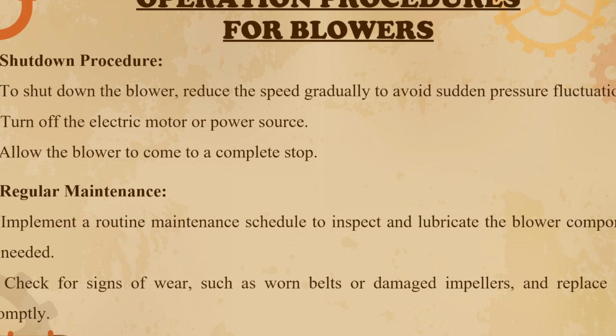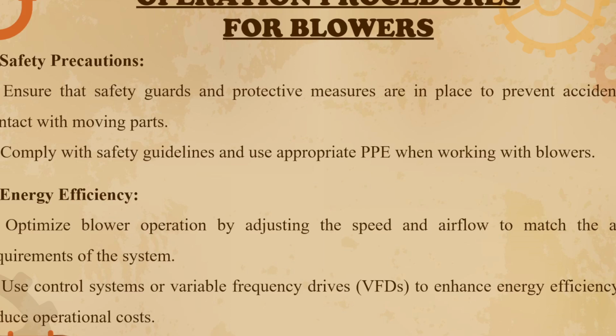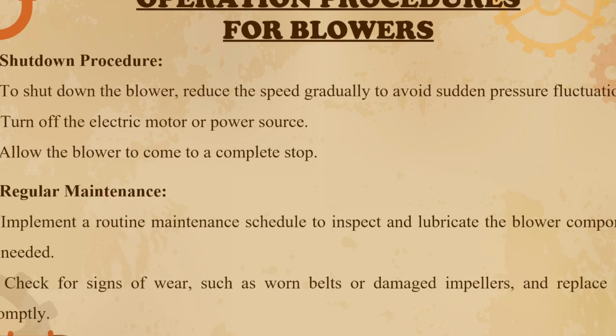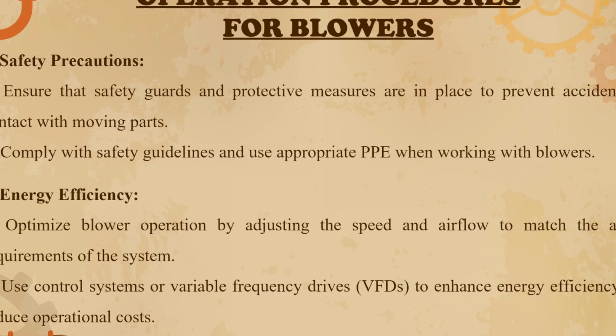Sixth procedure is to have regular maintenance. Implement a routine maintenance schedule to inspect and lubricate the blower components as needed. Check also for signs of wear, such as worn belts or damaged impellers, and replace them promptly. Seventh procedure is the safety precaution. We must also ensure that safety guards and protective measures are in place to prevent accidents or contact with moving parts. Comply with safety guidelines and use appropriate PPE when working with blowers.